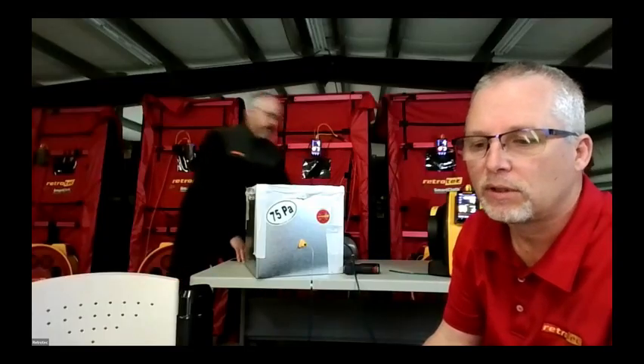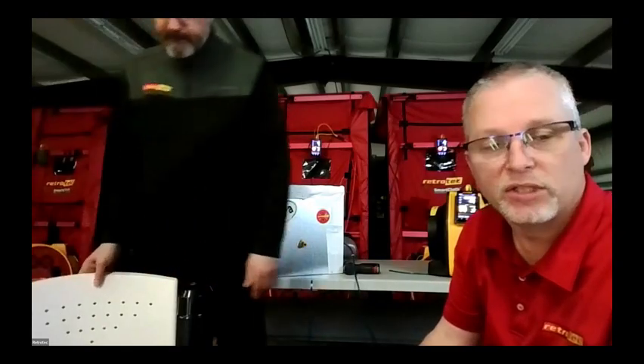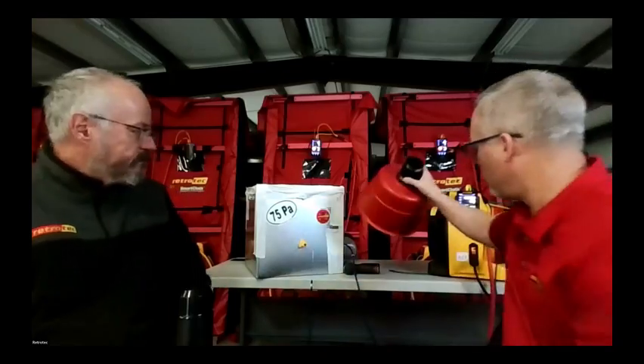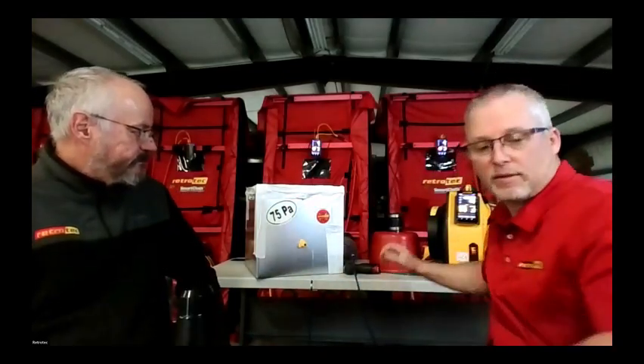you can hook multiple units up in parallel, and that will give you the opportunity to test larger systems. Recently I talked with a customer that was testing a very large air handler, and they had 10 units hooked up to it in parallel. That would give them about 3,000 CFM of flow. Others have used 2 or 3, but putting them in series, one blowing into the next, does not help you. You need to hook them up in parallel. It's been a very popular unit. It helped us get more into the HVAC market.